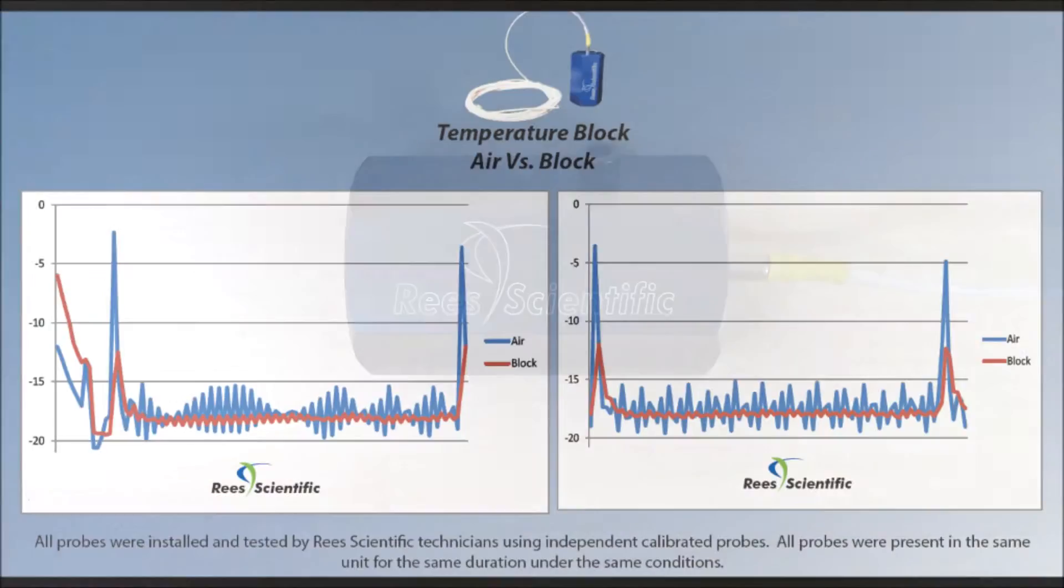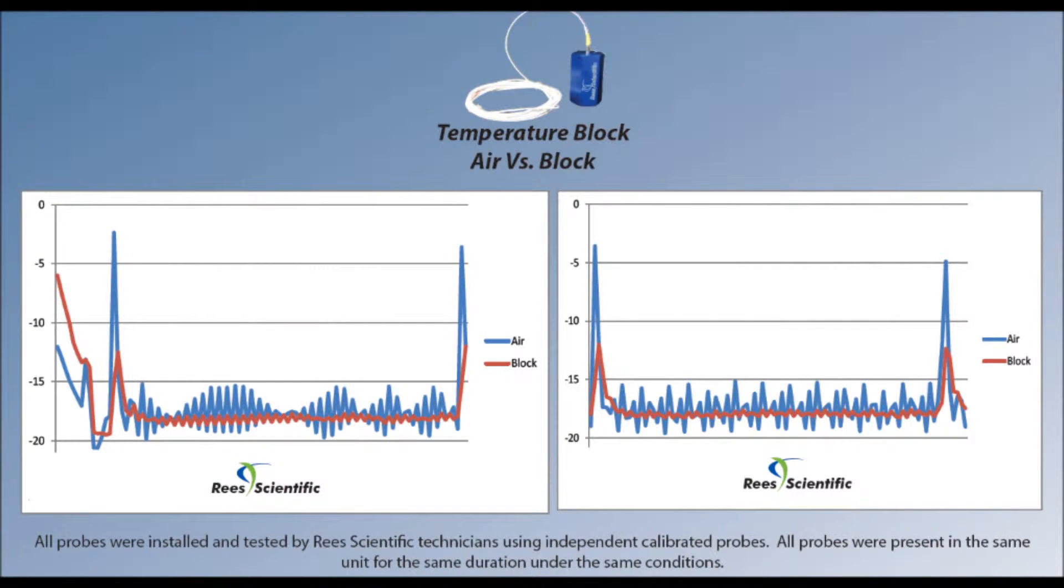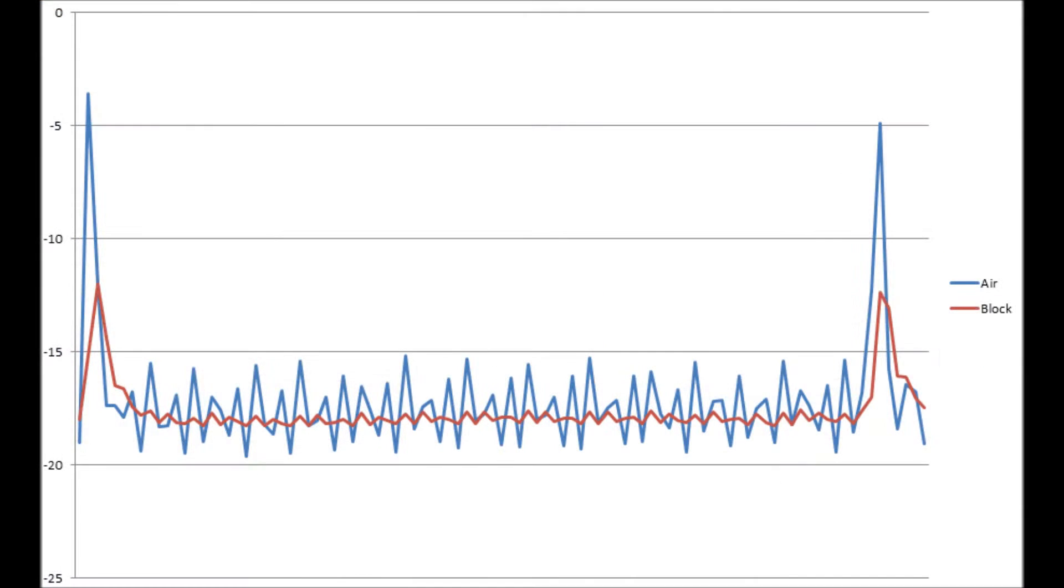Normal events like the opening and closing of freezer doors can cause fluctuations in temperature readings, and that may not be your goal when monitoring your equipment. The Rees Scientific Temperature Block will provide you with readings that more closely mimic the temperatures that your products are experiencing rather than the air surrounding them.